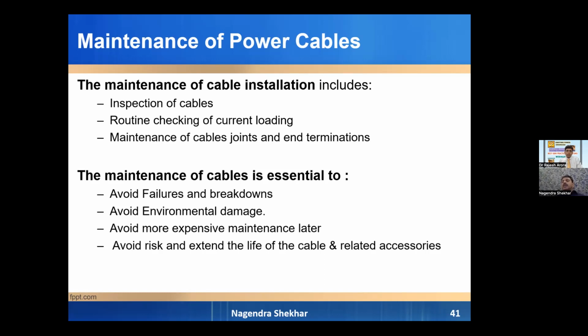Most of the cables become faulty either because of third party excavation, where they dig and damage our cable, or at cable terminations where our termination joints fail, because we do not take care of our terminations once they are made and connections are made. Ultimately, when they fail, it results in a breakdown, then we take care of it or we make it again. Why is this maintenance of cable essential?